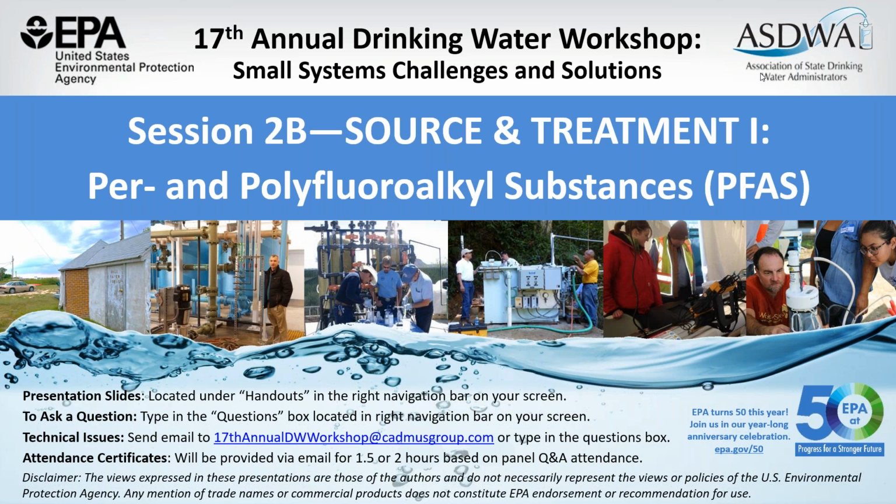I would understand that at the effluent, because I could see that you were getting PFBA driven in the upper portion of the contactor. But if that PFBA is coming off the contactor in the upper regions, and we've already established that the lower regions are exhausted with PFBA, I don't know what's slowing that up. So that's something that I would like to take a deeper look at. And I'm wondering if it has something to do with the relatively low loading rates that we have for this particular system. Okay, great. Yeah, makes sense.